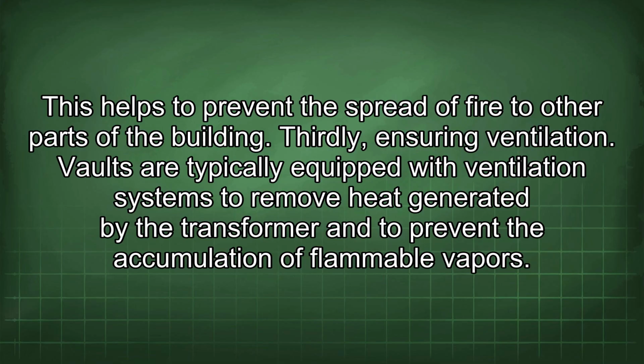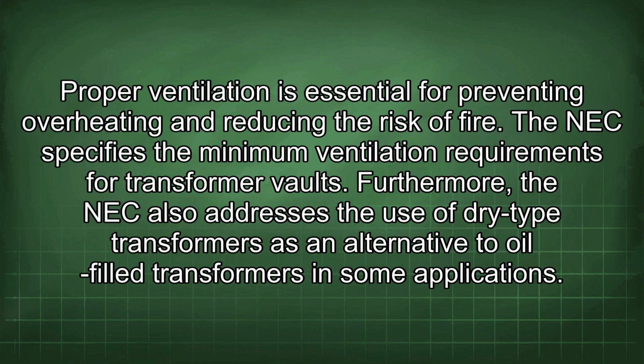Thirdly, ensuring ventilation. Vaults are typically equipped with ventilation systems to remove heat generated by the transformer and to prevent the accumulation of flammable vapors. Proper ventilation is essential for preventing overheating and reducing the risk of fire. The NEC specifies the minimum ventilation requirements for transformer vaults.